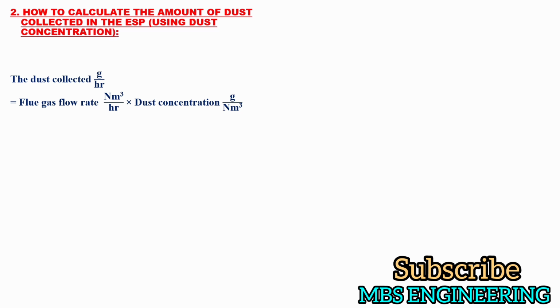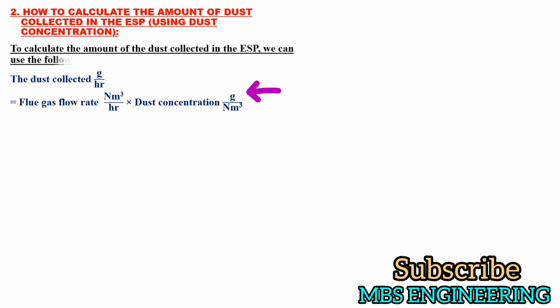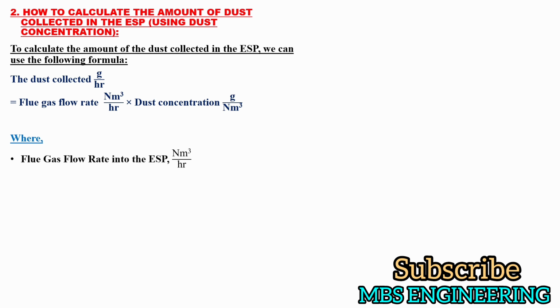Next, we will learn and understand how to calculate the amount of dust collected in the ESP using dust concentration. To calculate the amount of dust collected in the ESP, we can use the following formula. The dust collected in grams per hour is equal to the flue gas flow rate in Newton meter cube per hour multiplied by the dust concentration in grams per Newton meter cube. Where the flue gas flow rate into the ESP is in Newton meter cube per hour, and the dust concentration is in gram per Newton meter cube.